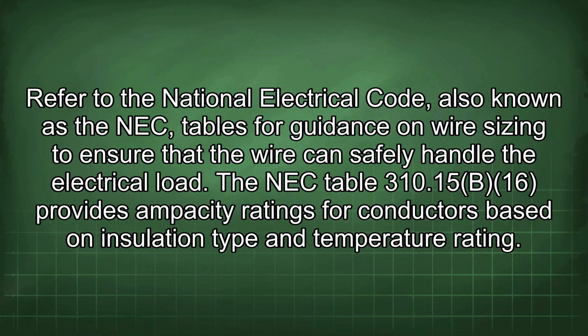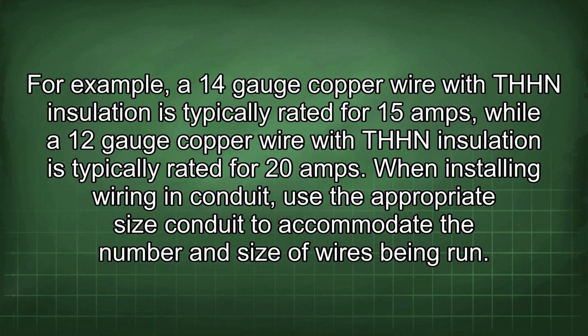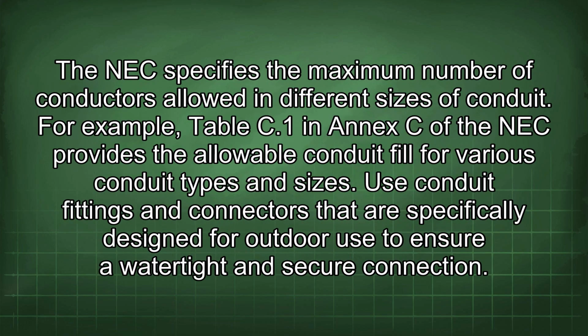The NEC Table 310.15(B)(16) provides ampacity ratings for conductors based on insulation type and temperature rating. For example, a 14-gauge copper wire with THHN insulation is typically rated for 15 amps, while a 12-gauge copper wire with THHN insulation is typically rated for 20 amps. When installing wiring in conduit, use the appropriate size conduit to accommodate the number and size of wires being run. The NEC specifies the maximum number of conductors allowed in different sizes of conduit.